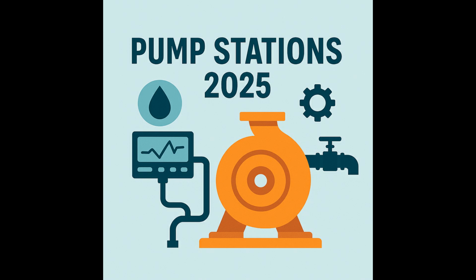Absolutely. One of the biggest is that exact efficiency versus reliability trade-off you just mentioned. Sometimes running at peak efficiency can conflict with those vital operational safety margins. Makes sense. Then there's daily variability. Demand cycles, they rarely match the perfect static design assumptions. This pushes pumps to frequently operate outside their best efficiency point, or BEP, where they perform their best. Okay, the BEP. And all of this leads directly to asset degradation. Inefficient operations increase vibration, they raise the risk of cavitation, which we'll definitely talk more about, and ultimately, they lead to the premature failure of parts. So it's a constant balancing act.